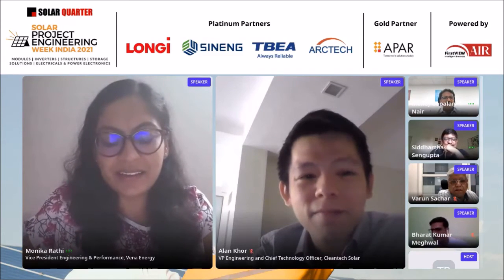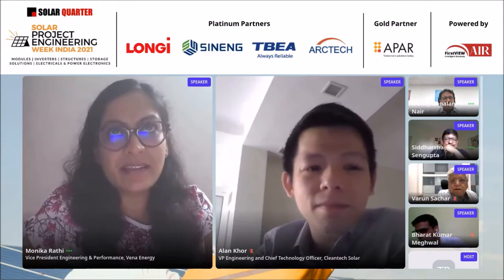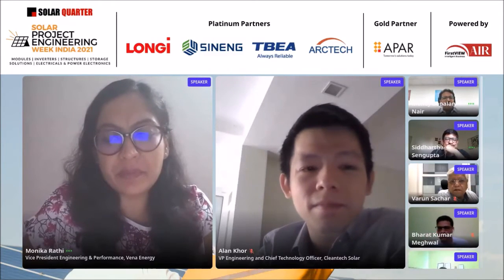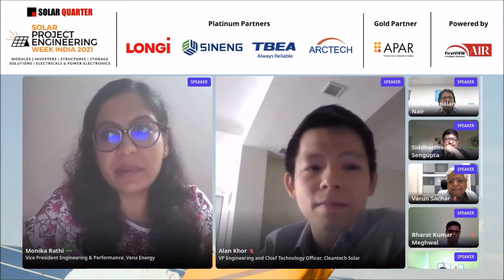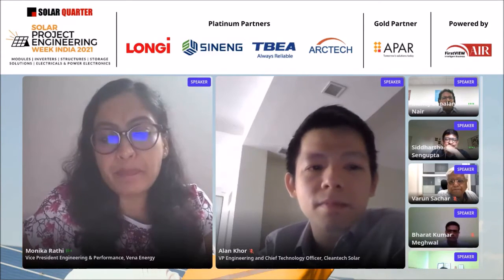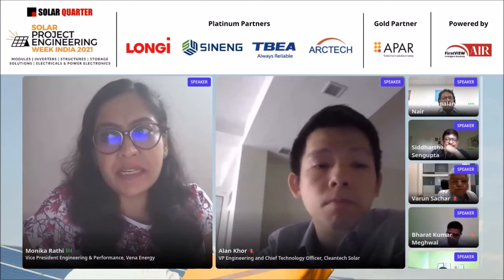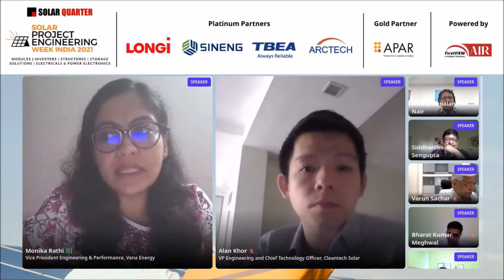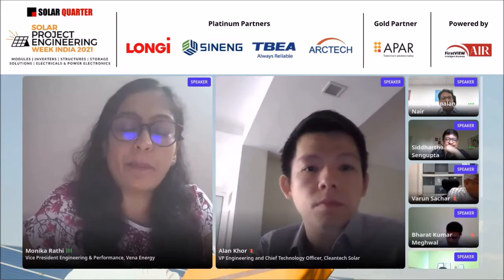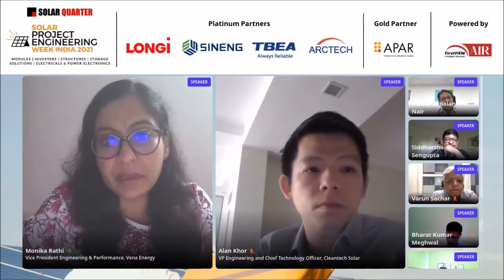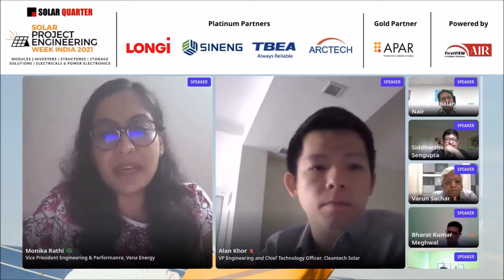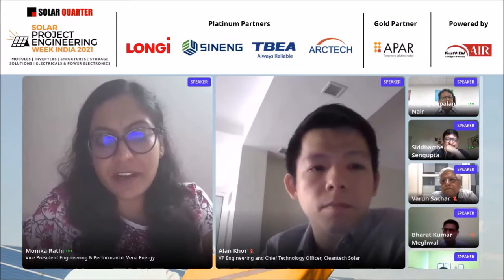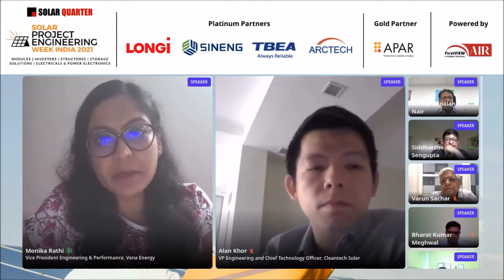Thank you, Alan. I think it was great to hear that you are taking care of the increased current values while designing the compatibility between modules and inverters. This brings me to actually one more point which we end up missing out. It is very critical to ensure that my modules and inverters, even from an operating voltage perspective, are compatible, right? We know that the inverter efficiency is dependent on the operating voltage. The MPPT, again, it's a combination of multiple MPPTs in string inverter versus maybe one in the central inverter.